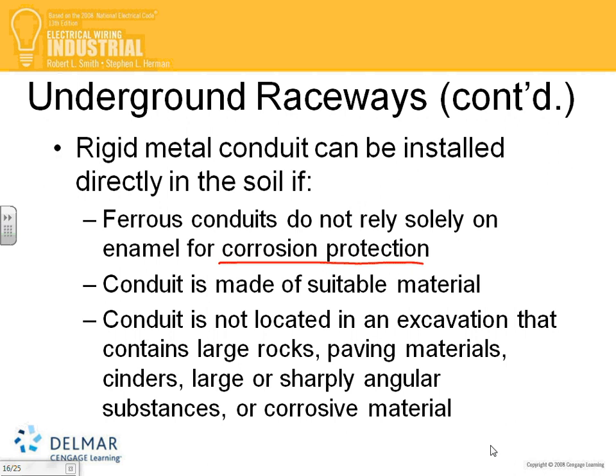So, a couple of things, guys, you're going to pay attention. For example, if you have a lot of large rocks and you're using schedule 40, and you start burying these conduits with big, large rocks, there is a possibility you're going to damage that schedule 40 or 80, as a matter of fact. So pay attention to when you bury it. There's a whole way of burying it, guys, excavation and adding material to bury it.